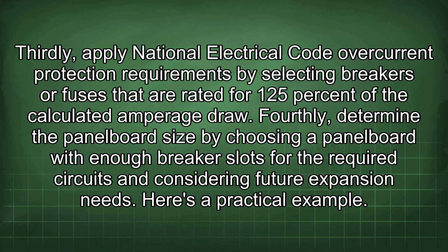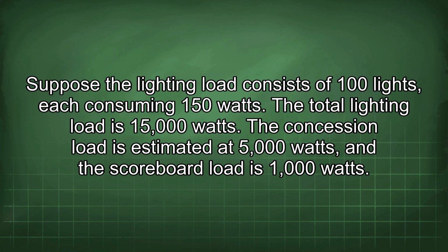Thirdly, apply National Electrical Code overcurrent protection requirements by selecting breakers or fuses that are rated for 125% of the calculated amperage draw. Fourthly, determine the panel board size by choosing a panel board with enough breaker slots for the required circuits and considering future expansion needs. Here is a practical example. Suppose the lighting load consists of 100 lights, each consuming 150 watts. The total lighting load is 15,000 watts. The concession load is estimated at 5,000 watts, and the scoreboard load is 1,000 watts.